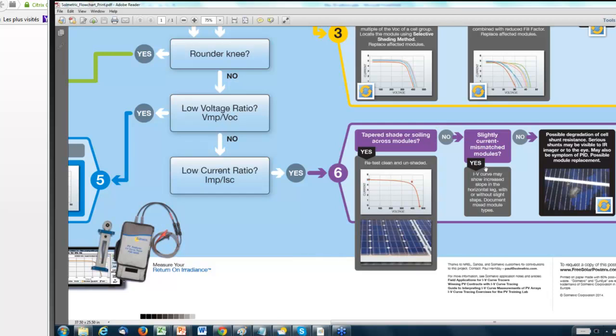then you move to the right and check if you have possibly slightly current mismatched modules in your array. Suppose you have an array like we have at the fire station near us that has had so many failures over the years in its modules that there are 3 different types of modules that have been used in the same string. If they have a slightly different short circuit current, it's exactly the same effect as you have here. You may see a slope across the top leg of the curve with very little, if any, stepping.